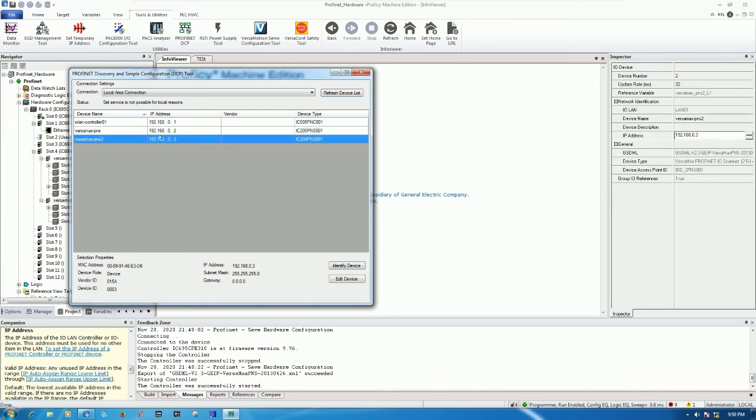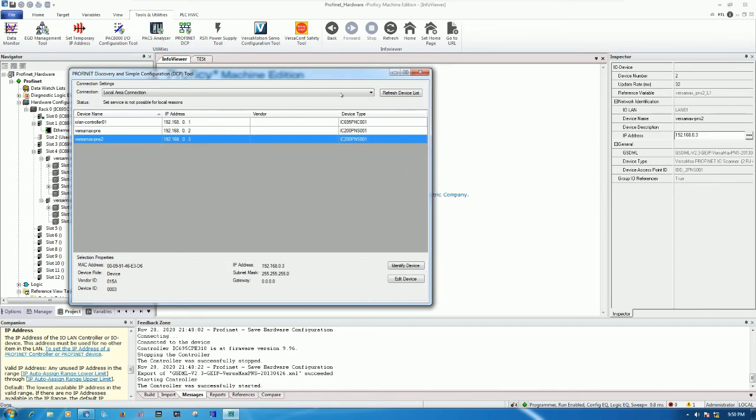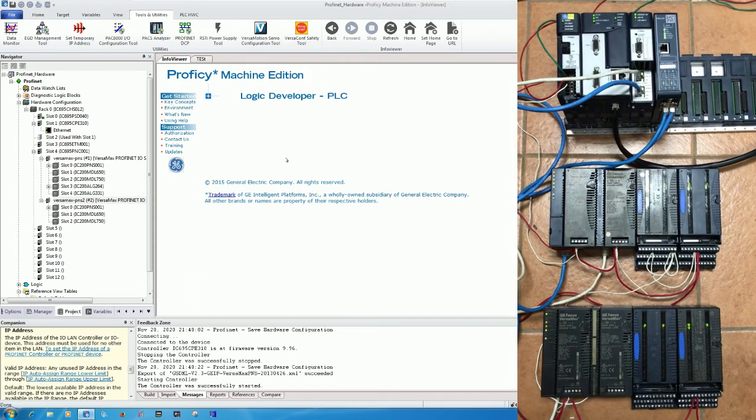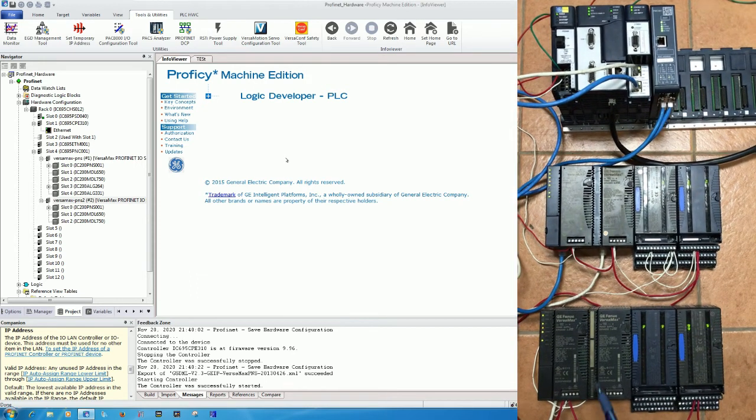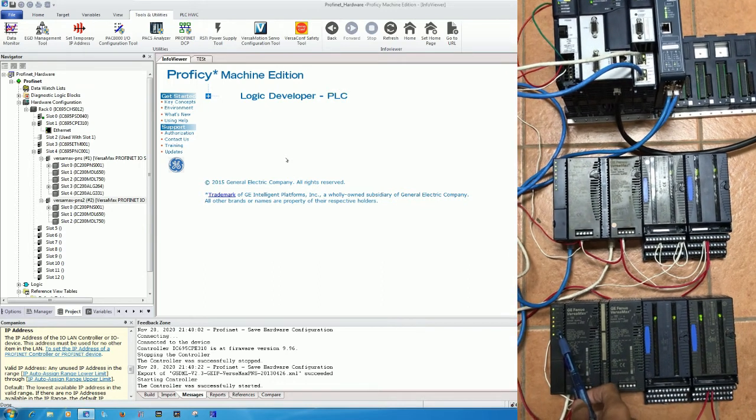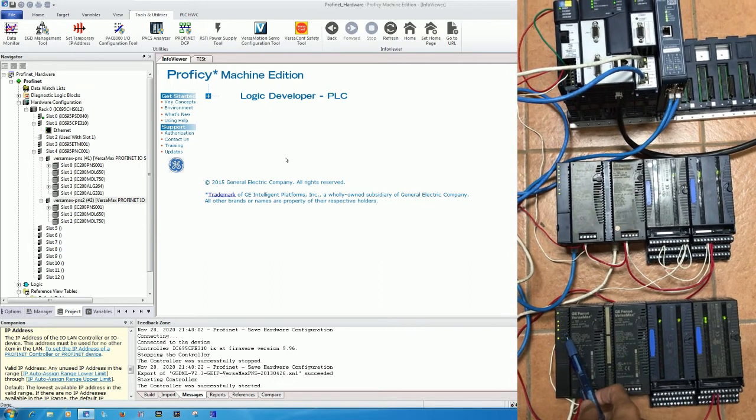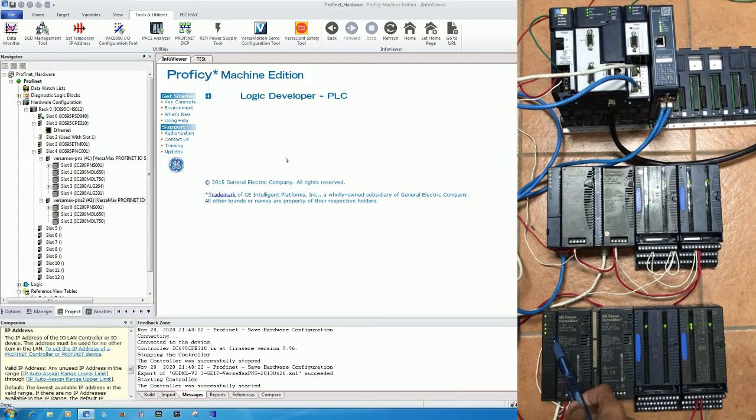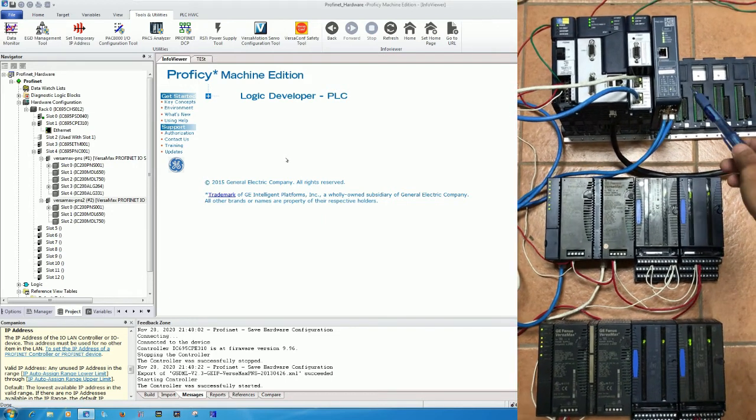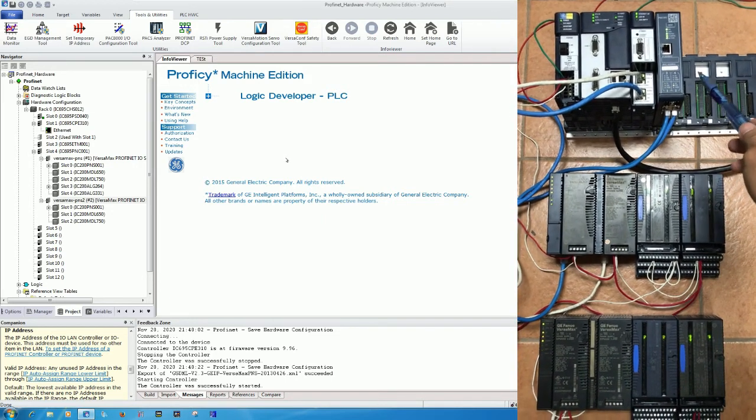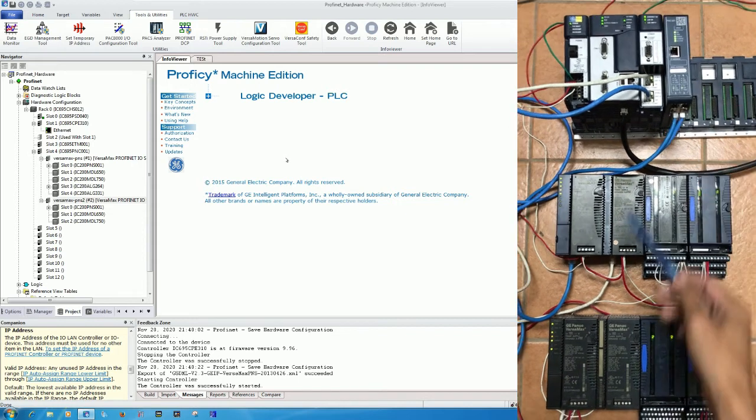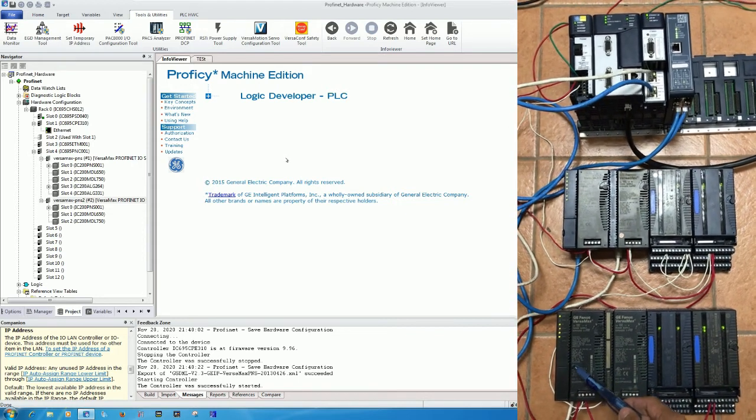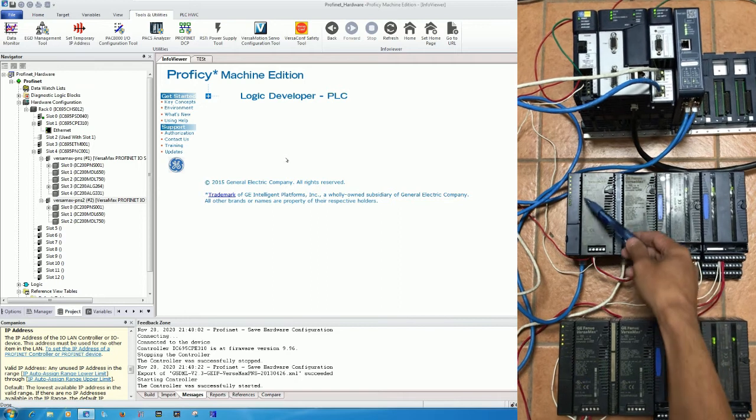Right now we already assigned the IP address and the name of the module for PNS number 2. Right now it shows the LED connect. You see here, it means that it can communicate between the Profinet controller and Profinet scanner number 2 and number 1 also.